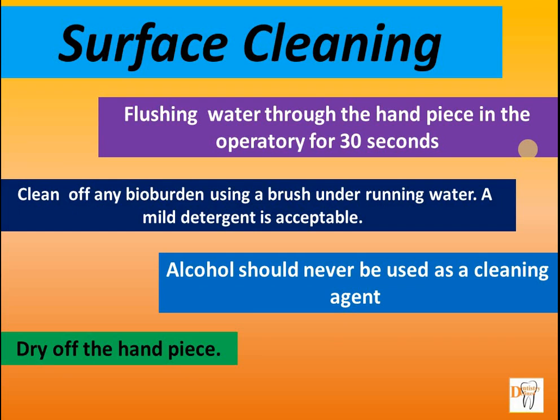Alcohol should never be used as a cleaning agent, as it can dehydrate spores and increase resistance to sterilization. Do not use any chemical solutions for cleaning, as foreign substances may have a detrimental effect on the sterilizer or the handpiece. Dry off the handpiece. It is an important step before chemiclaving or use of chemical agent for the sterilization, as excess water will allow oxidation to occur in the chamber leading to corrosion.